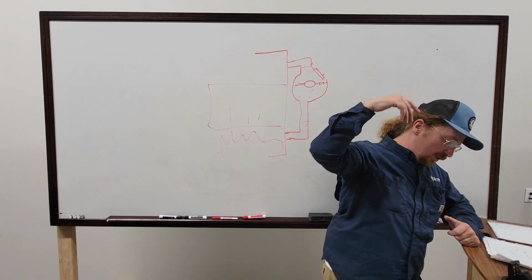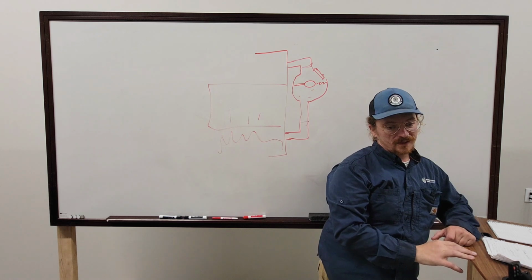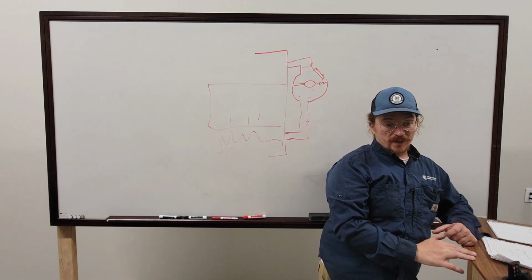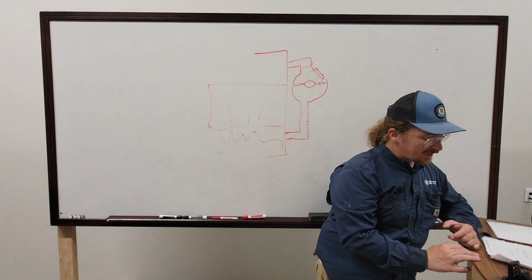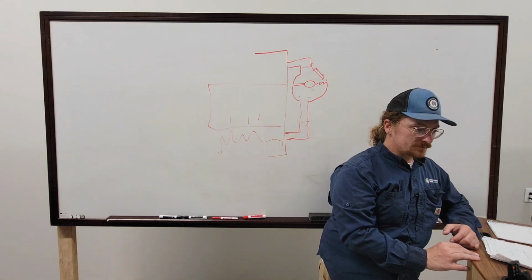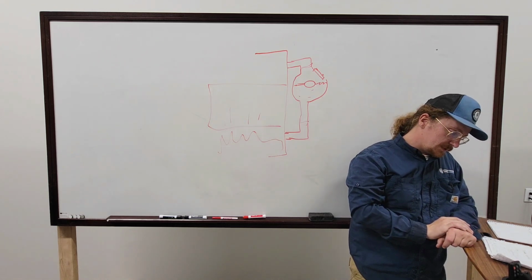All right, so airflow proofing. It's the same sort of pressure switches. Open contacts, close. Usually it's forced draft, so you want to verify that you have some sort of positive pressurized flue. Make sure you don't have a blockage.